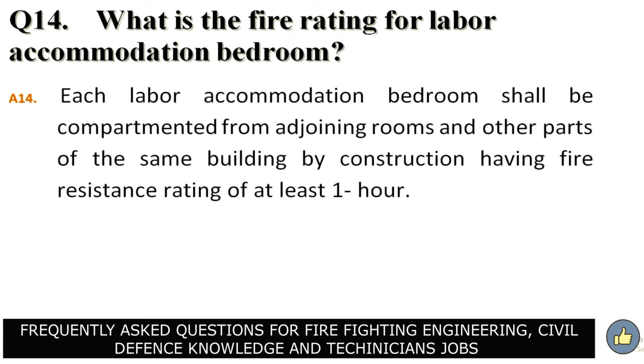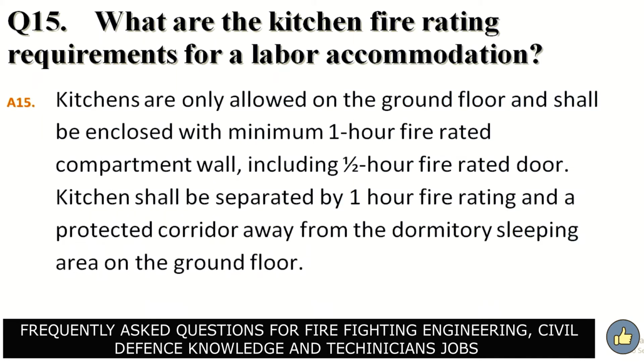What is the fire rating for labor accommodation bedroom? Answer. Each labor accommodation bedroom shall be compartmented from adjoining rooms and other parts of the same building by construction having fire resistance rating of at least 1 hour. What are the kitchen fire rating requirements for labor accommodation? Answer. Kitchens are only allowed on the ground floor and shall be enclosed with minimum 1 hour fire rated compartment wall, including half-hour fire rated door.